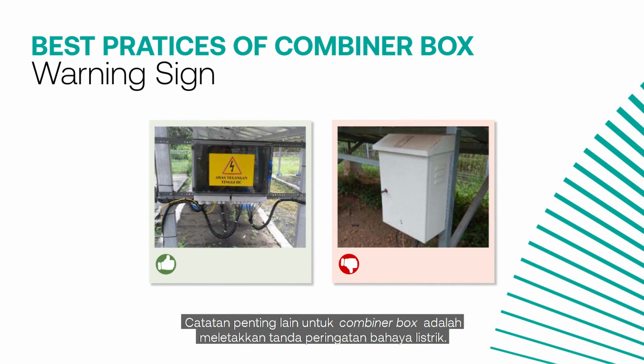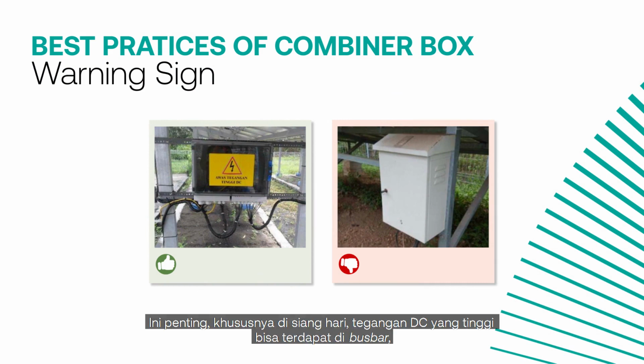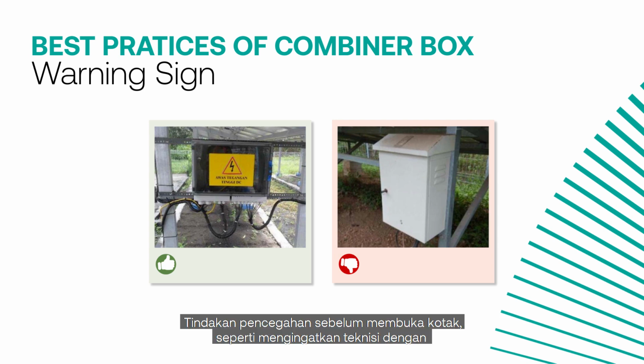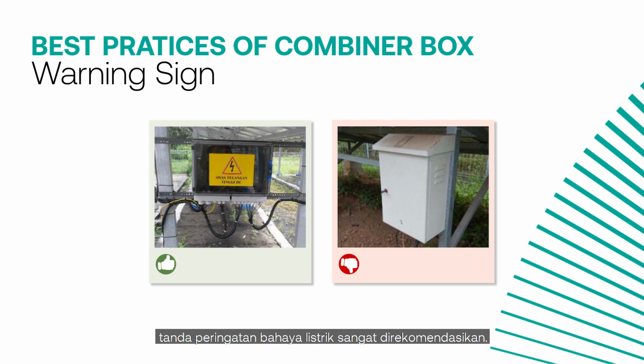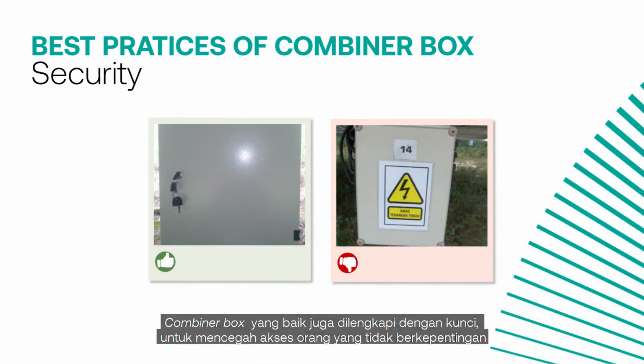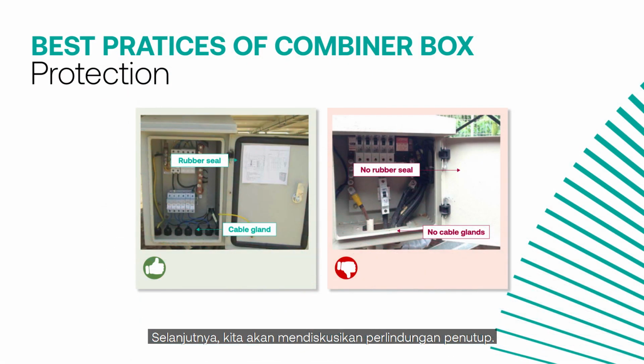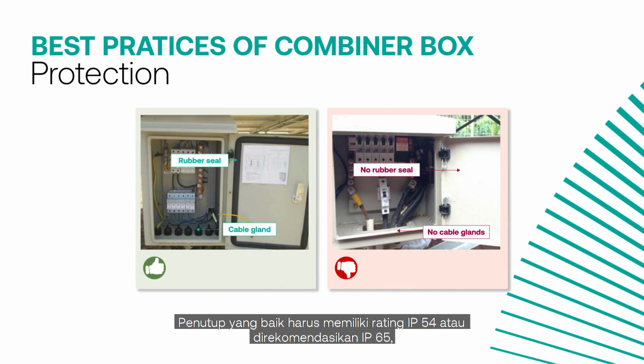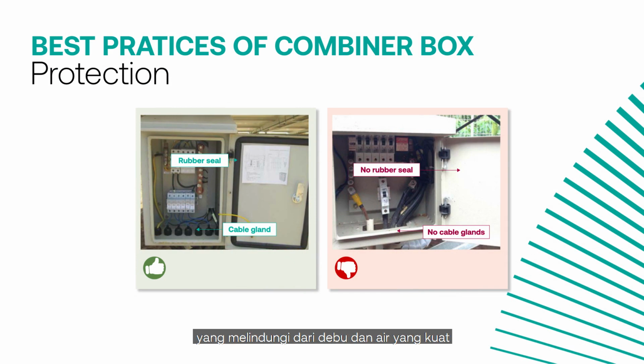Another important note for combiner box installation is to put up a warning sign of electrical hazard. This is especially important as during the day, high voltage DC may exist on the busbar or non-isolated live conductors inside the combiner box. Preventive measures before opening the box, such as alerting technicians with a warning sign of electrical hazard, are strictly recommended. A good combiner box is also equipped with a lock to prevent access from unauthorized persons. Next, we will discuss the enclosure protection. A good enclosure should be rated IP54 class or the recommended IP65 class that protects against dust and powerful water jets.